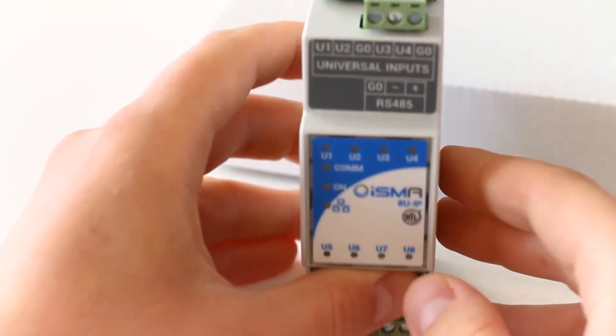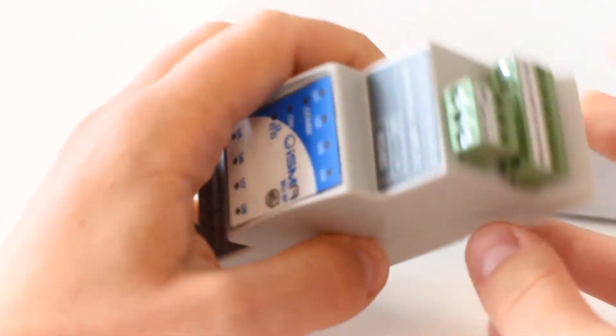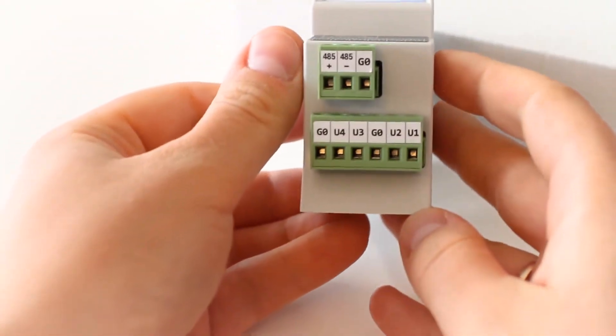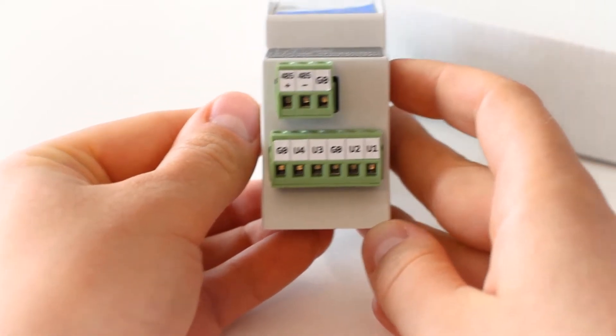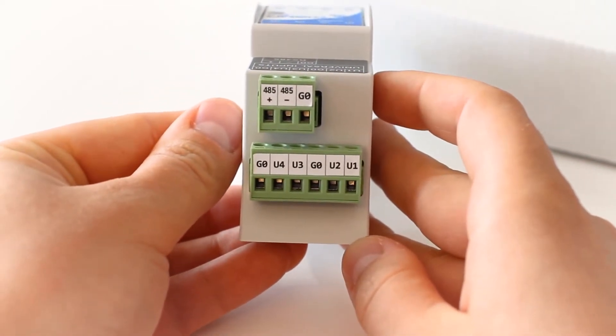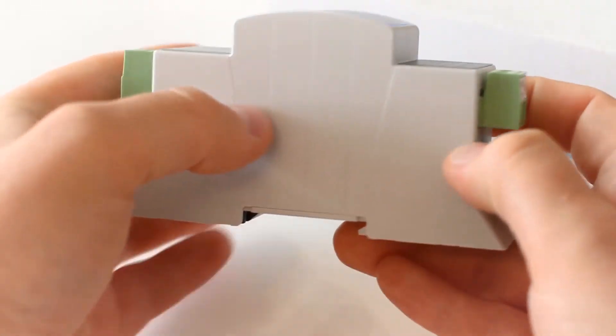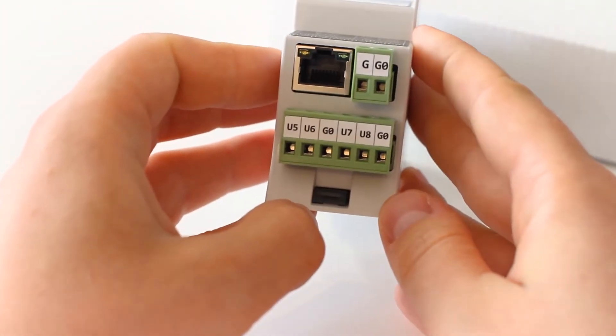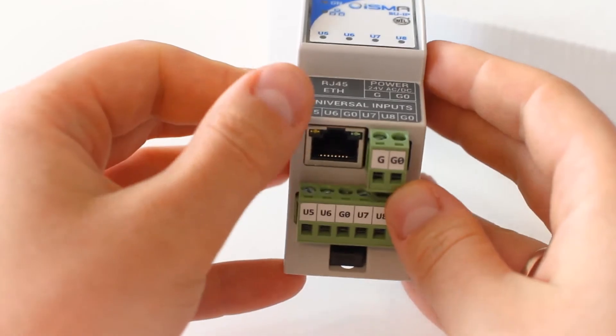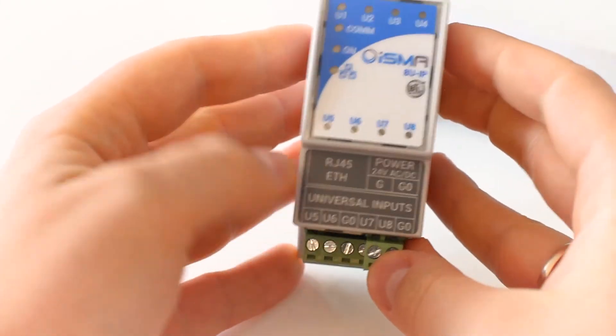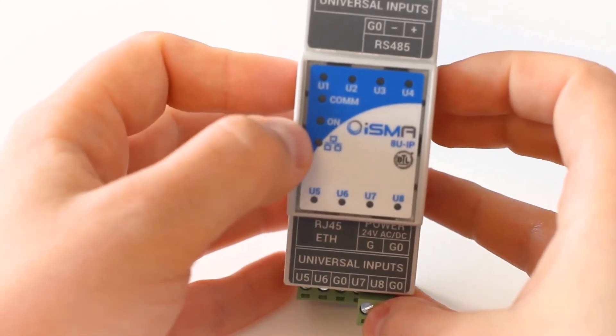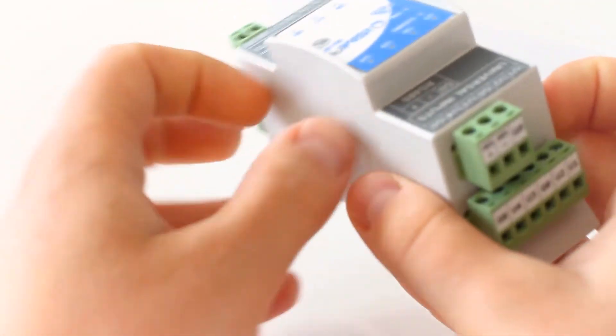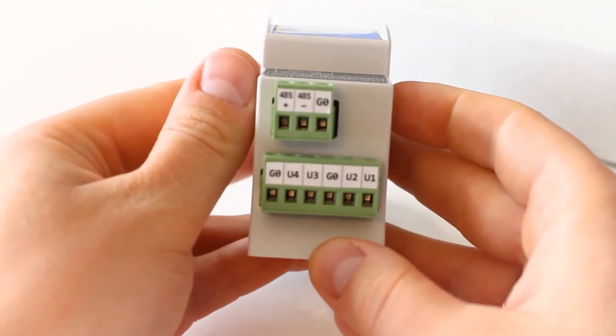There is an RS-485 port for Modbus TCP IP to RS-485 gateway at the top of the device, along with the four UI terminals. Another four UI terminals are located at the bottom of the device, next to the Ethernet port and 24V AC-DC input. It's a multi-protocol I.O. module equipped with BACnet and Modbus.